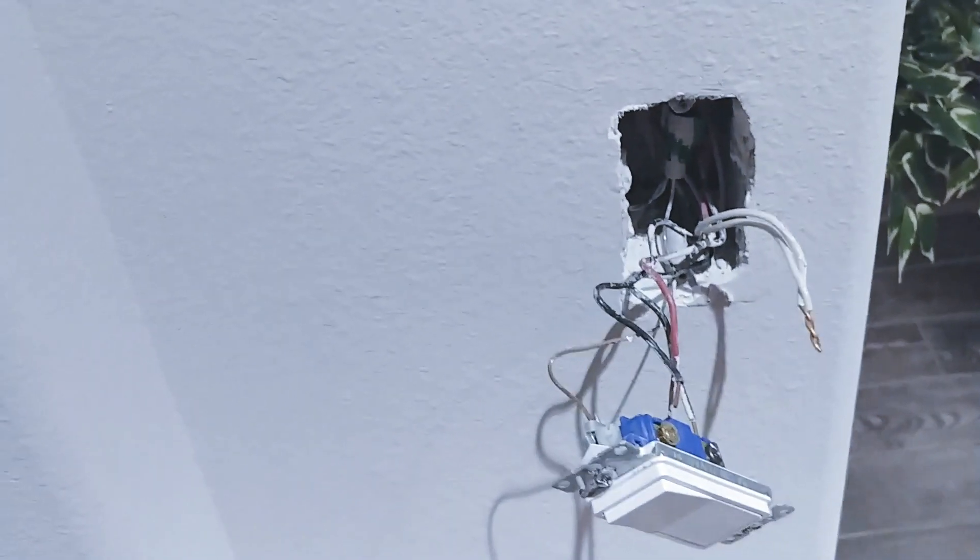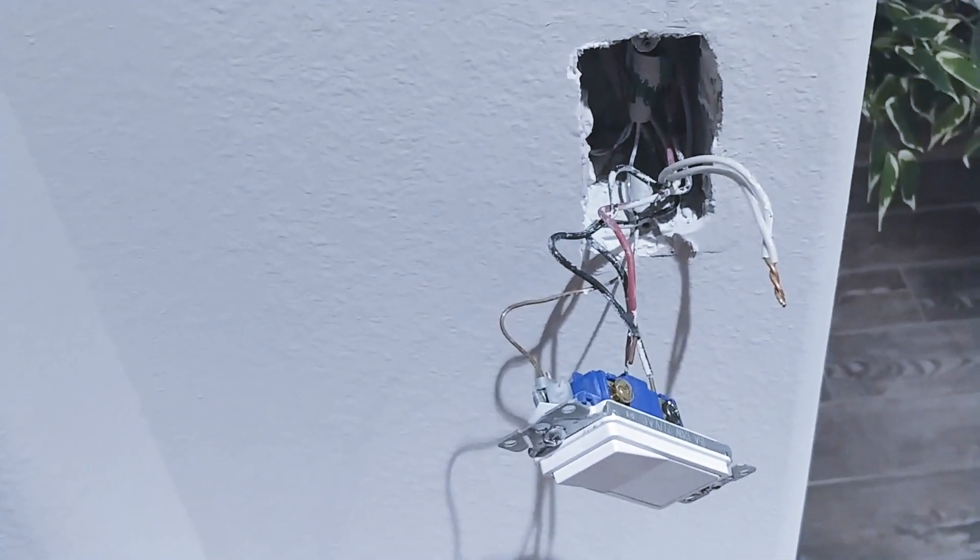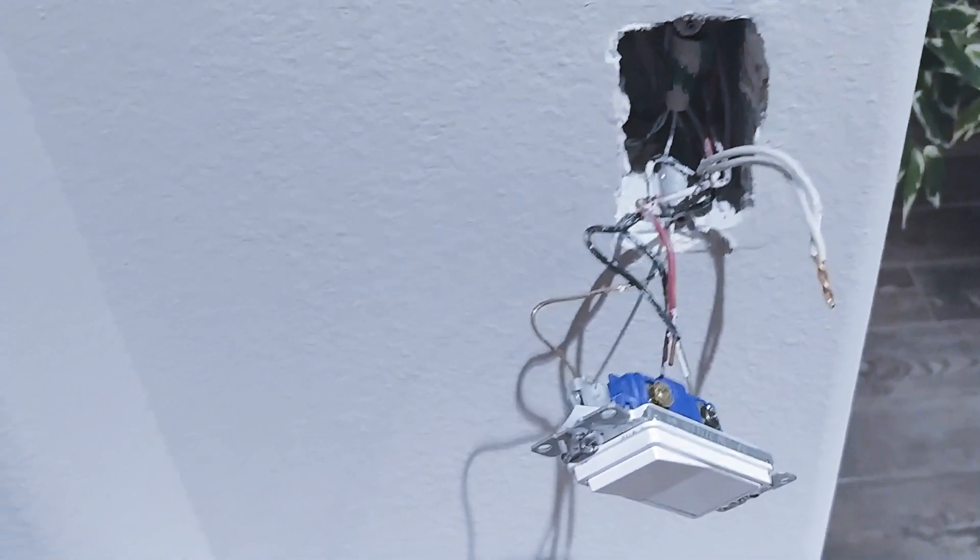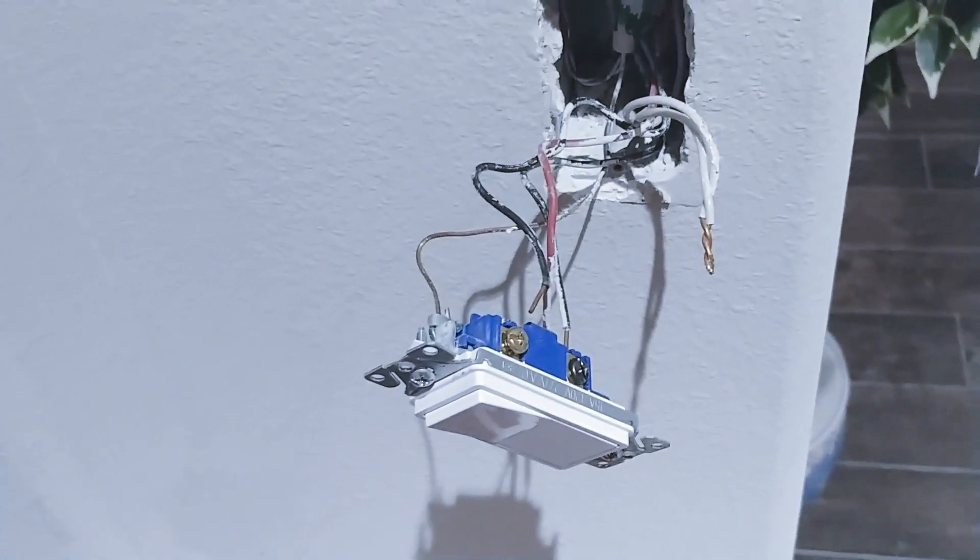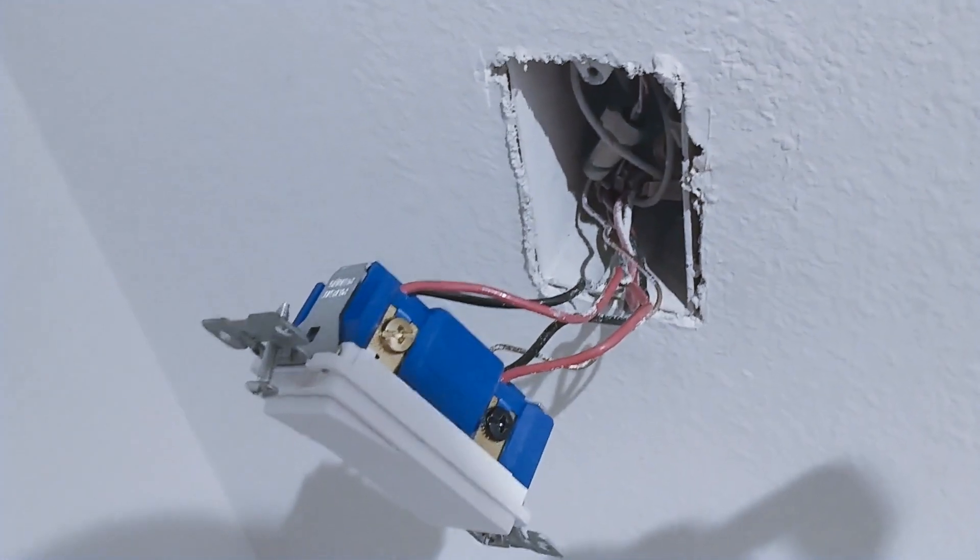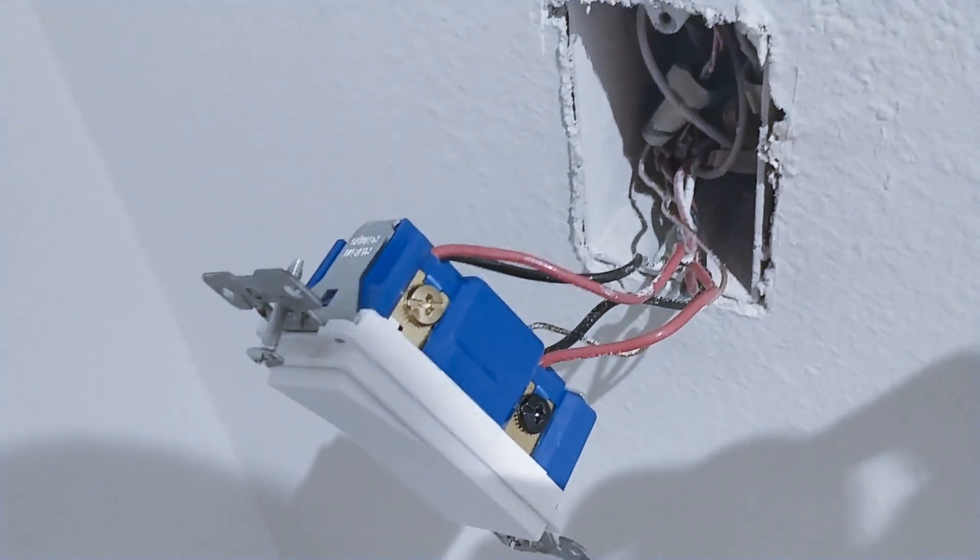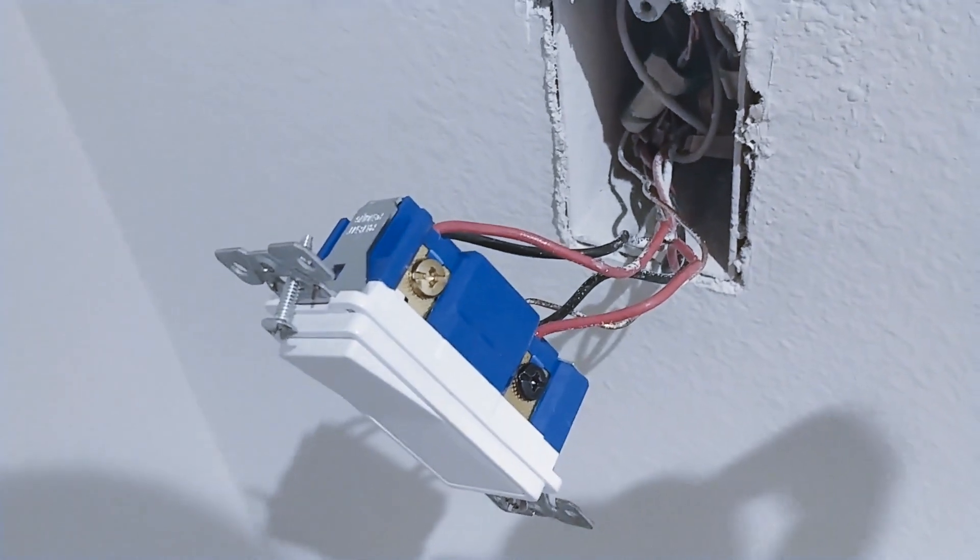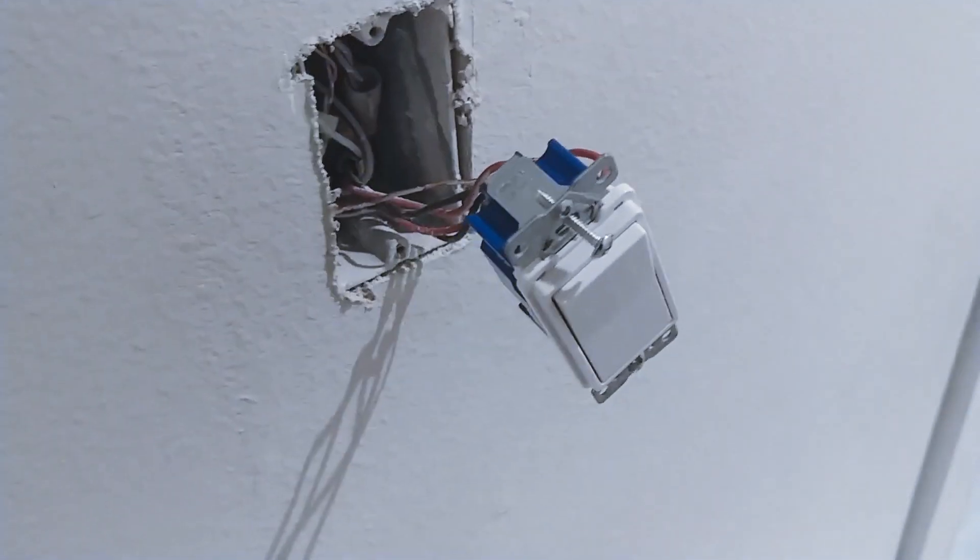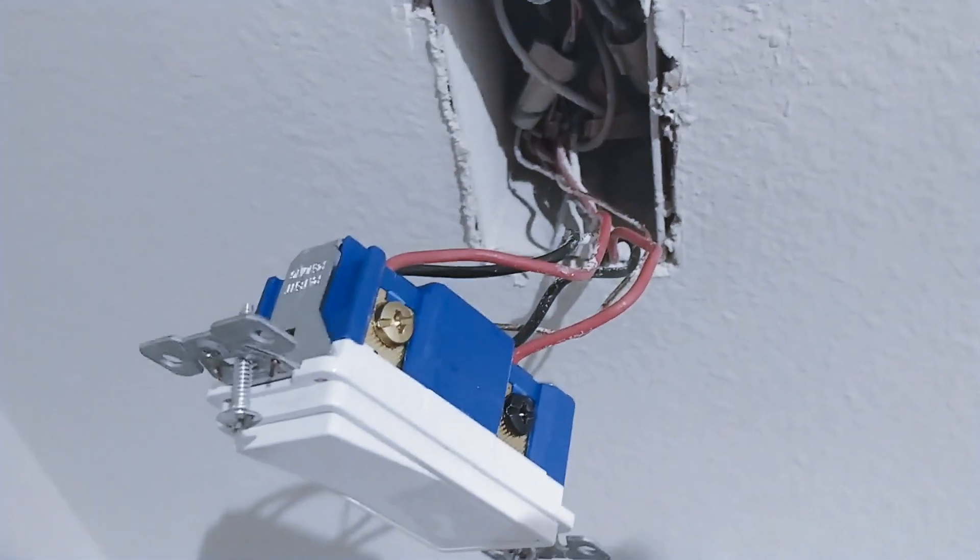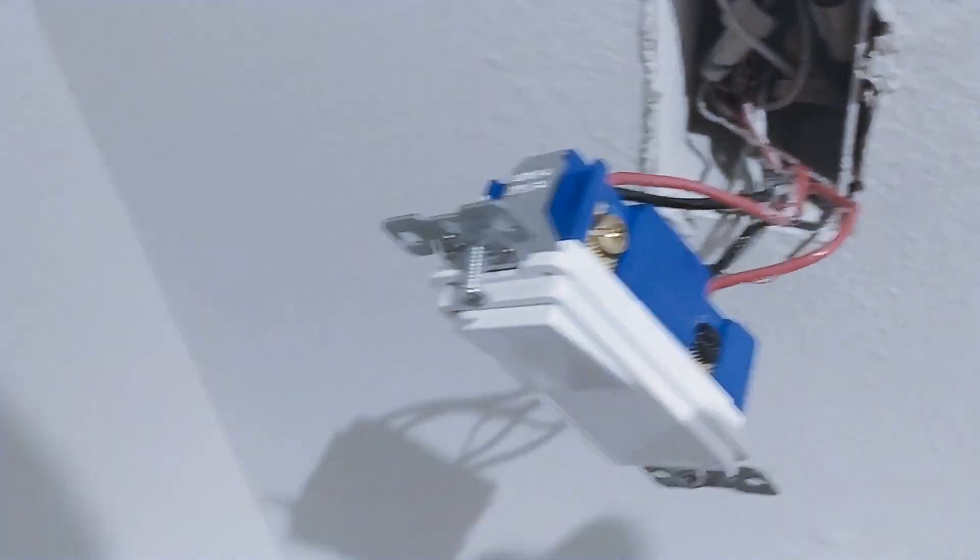So this is more than likely the load but it's also gonna be a matter of trial and error. I may not always get it right. So we'll look at the other switches. Okay this is definitely the middle switch. The reason why is you see two red wires coming off of it. So I've got two travelers on this one. This is gonna be my middle switch even though it has four wires coming off of it, it's actually a three-way switch not a four-way. That's really confusing but this is definitely the middle switch.